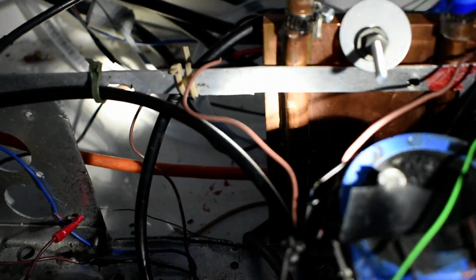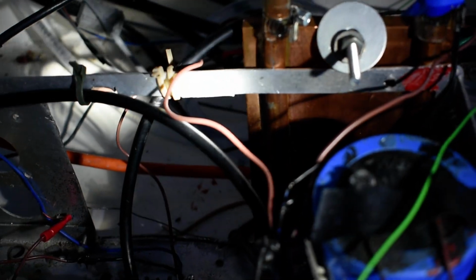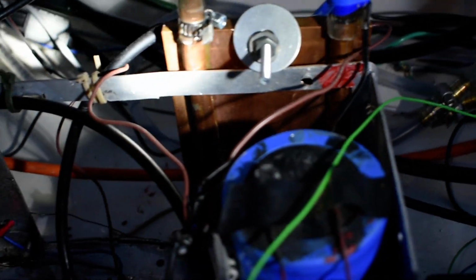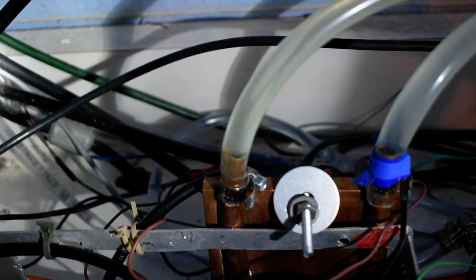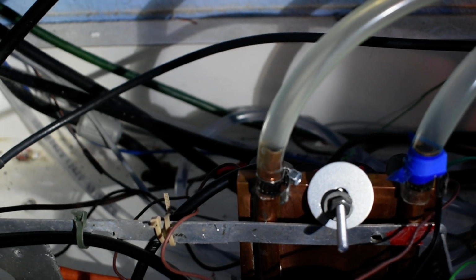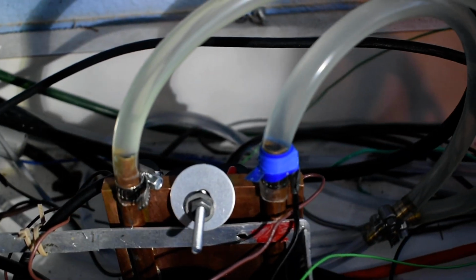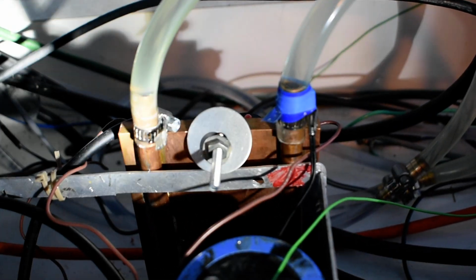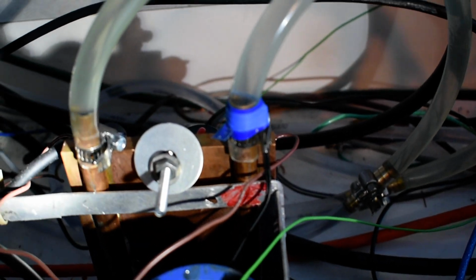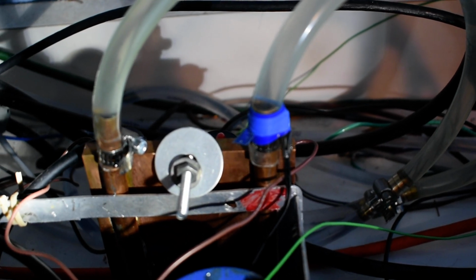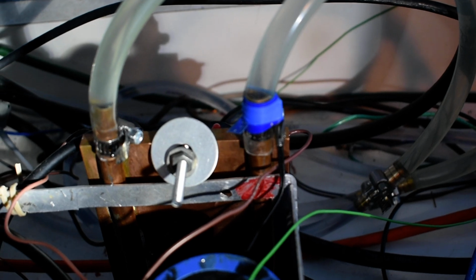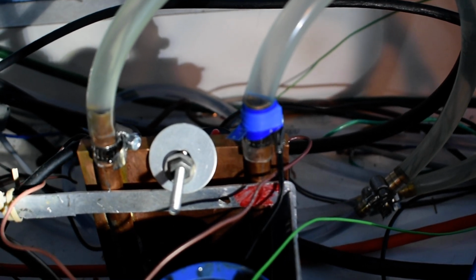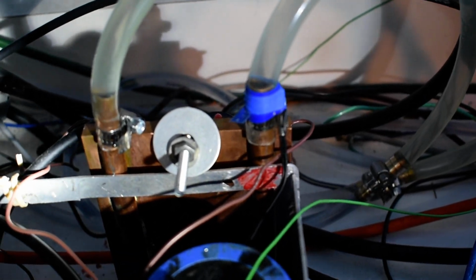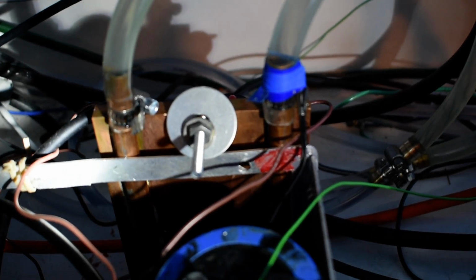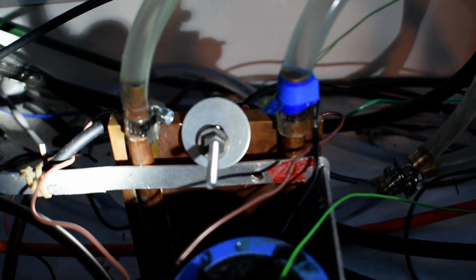And then back here, I'll highlight this so you can see the copper tubing soldered onto the back of the copper spreader. This is the input line with distilled water, and this is the output line. And the temperature probe is tied to it, so we're really monitoring the output water temperature, which pretty well corresponds with the temperature of the copper spreader.